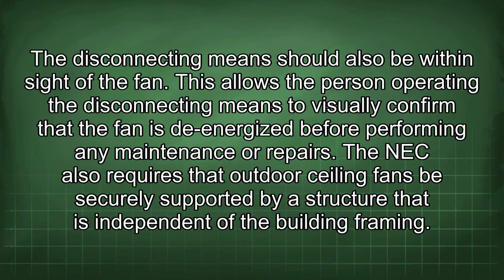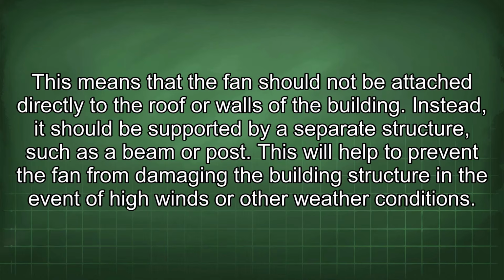The NEC also requires that outdoor ceiling fans be securely supported by a structure that is independent of the building framing. This means that the fan should not be attached directly to the roof or walls of the building. Instead, it should be supported by a separate structure, such as a beam or post. This will help to prevent the fan from damaging the building structure in the event of high winds or other weather conditions.